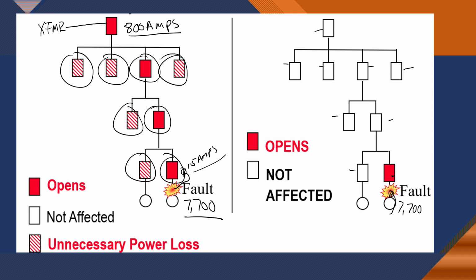Okay, so here we go. I have on this slide a 15 amp breaker I added, right here. If I have a 15 amp breaker and I have that fault that we talked about earlier, I have 7,700 amps coming to this fault.